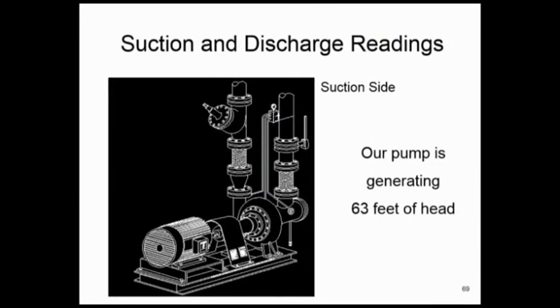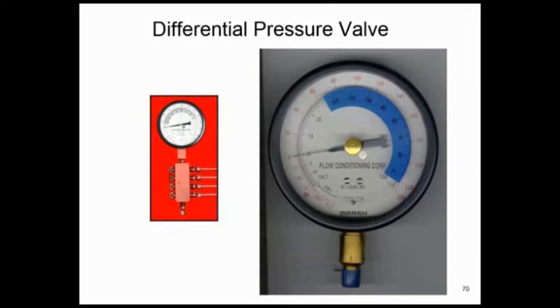Does that mean I'm underperforming? No, it doesn't. We have to look at flow in GPM, not head. So if I've got a fixed impeller size, which I already bought with my pump, that's what I showed you a little while ago, what would my flow rate be? Now, first of all, we would recommend you use some kind of common gauge, so you can get differential pressure with one gauge. This particular gauge, by the way, for a specific gravity of 1, has feet of head built into it for you, which makes it easier sometimes for maintenance people to understand and read versus PSI. Because all your pump curves are going to be in feet of head, and most of your gauges are going to be in pounds. So if you want to go back and forth, if you can assume that specific gravity is 1, like for water, you can buy a gauge that's got feet of head already built into it and make it easier for everybody to find your 63 feet.